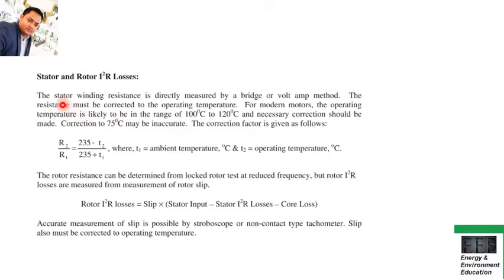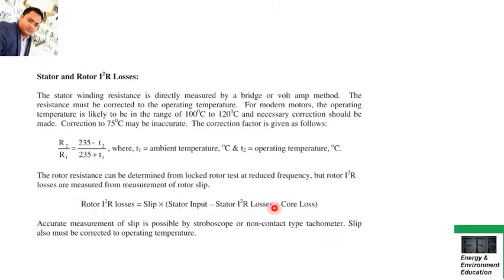Another important formula is for stator winding resistance: R2 divided by R1 equals (235 + T2) divided by (235 + T1), where T1 is the ambient temperature and T2 is the operating temperature, both in degrees centigrade. For the calculation of rotor I²R losses, the formula is: slip multiplied by stator input, minus stator I²R losses, minus core loss. You must memorize and understand this formula as they may ask various numerical questions from it.